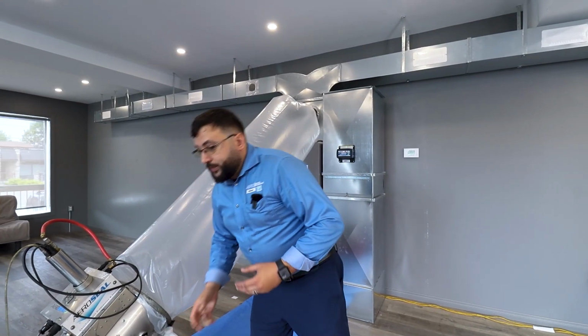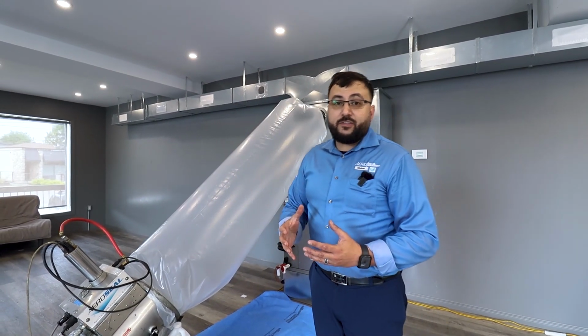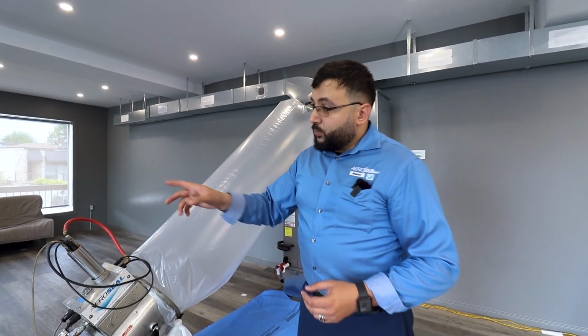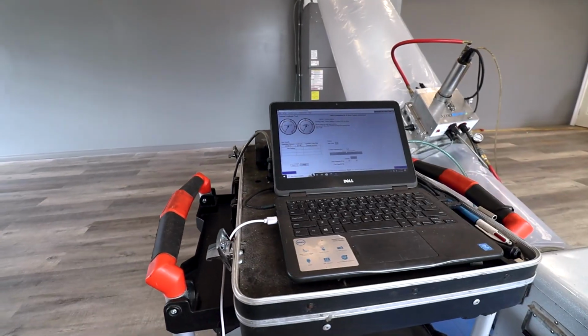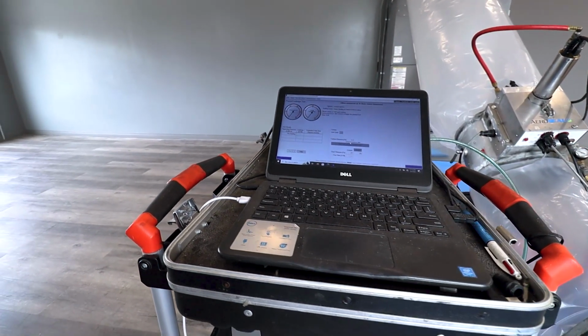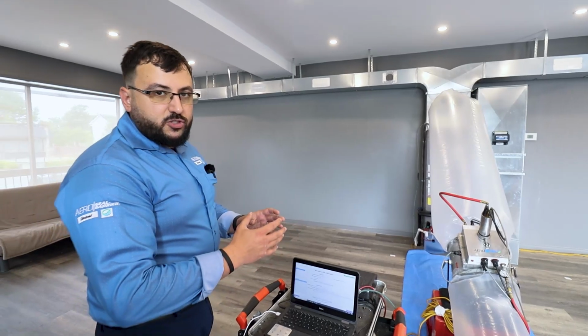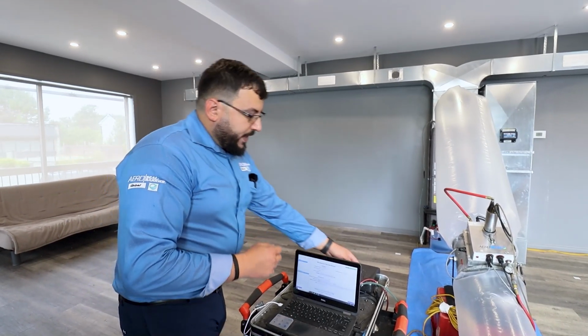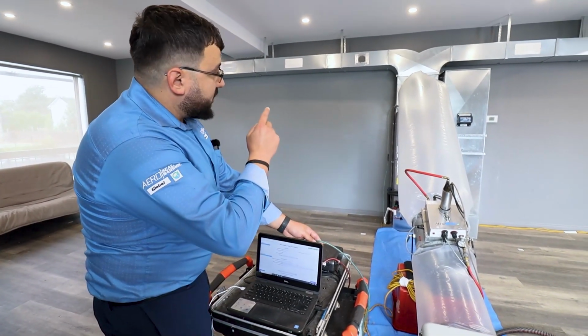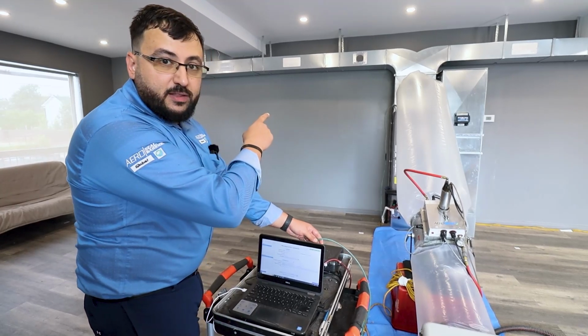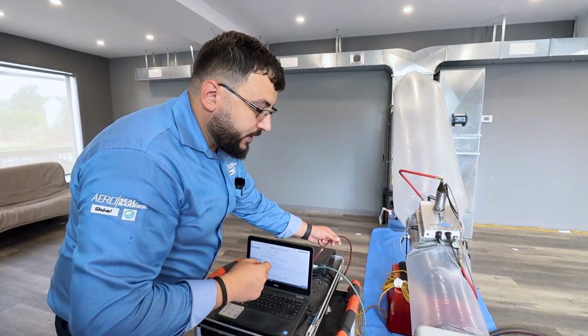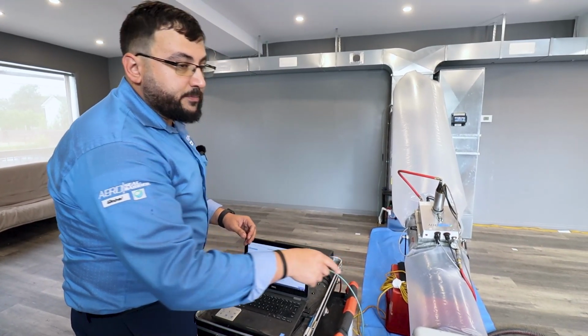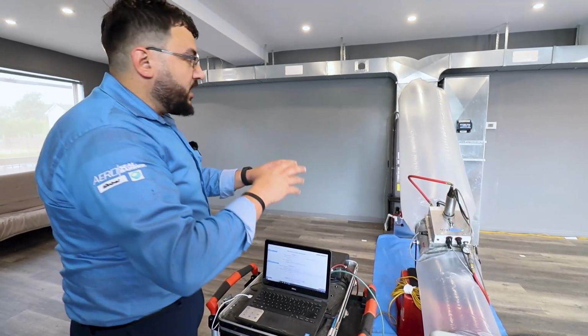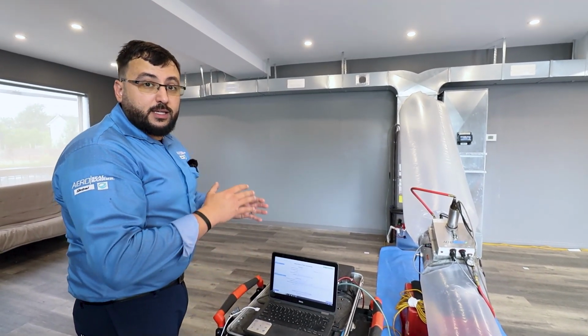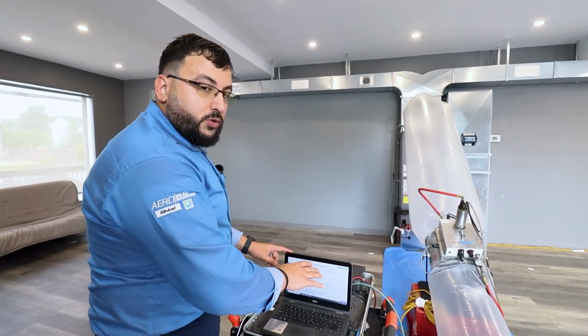So how do we know how much leakage there is in your ductwork? We have a computer here that measures the amount of air leakage in your ducts. We use a blue hose as a pressure sensor inside the ventilation, and a red one inside our fan box, and with the differentials we can tell how much your ducts are leaking.